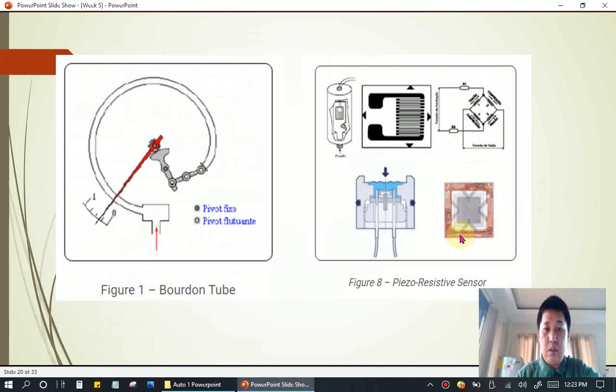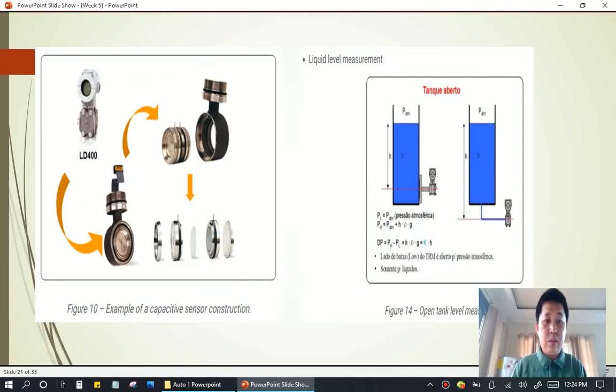We have also this, which is not a flow meter but a manometer or pressure gauge. We have the Bourdon tube pressure gauge, and here a piezoresistive sensor. We have also here an example of capacitor sensor construction. These measuring devices are converted into an electrical signal. Here we also have liquid measurement, open tank level measurement. Whatever the amount of content in the tank, there is a flow by gravity in here, and it measures the liquid level.